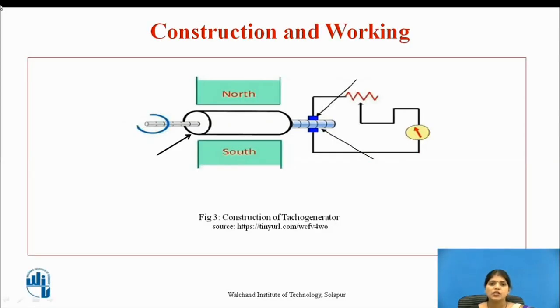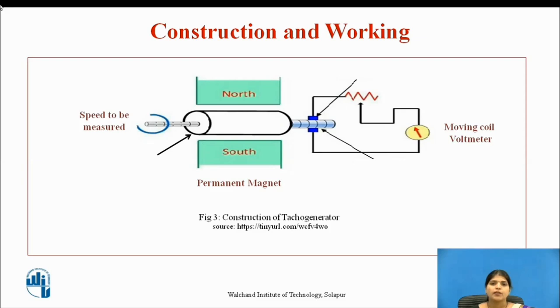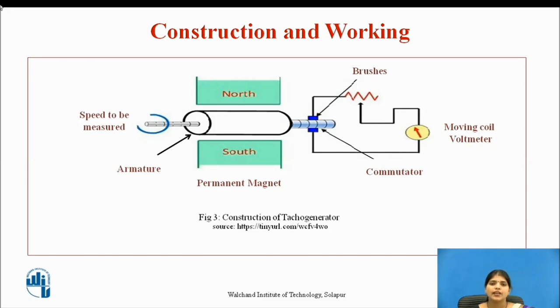The DC tachogenerator consists of a permanent magnet, a moving coil voltmeter, and a shaft for speed measuring — same as the AC tachogenerator, but no rectifier is needed because the output is already in DC form. A series resistance is used to limit the current under output short circuit condition. The polarity of the output voltage indicates the direction of rotation. The commutator collects current from the armature conductors and converts the internally induced AC EMF into DC EMF. Brushes collect current from the commutator and make it available to the external circuitry.